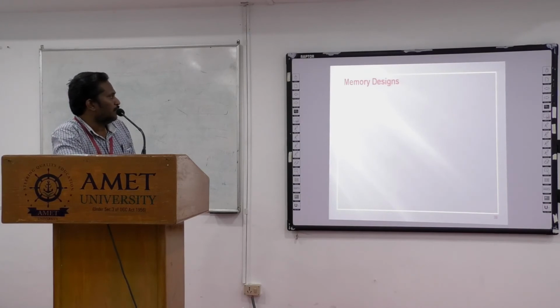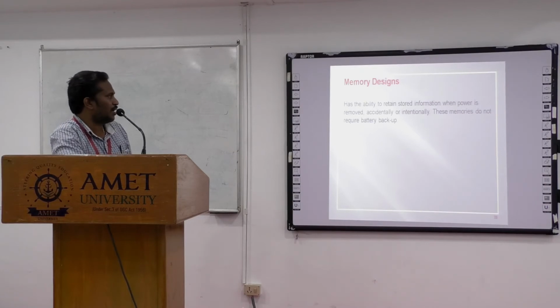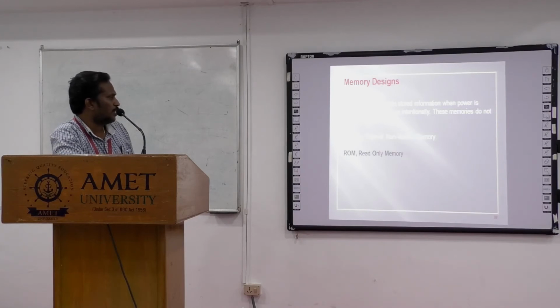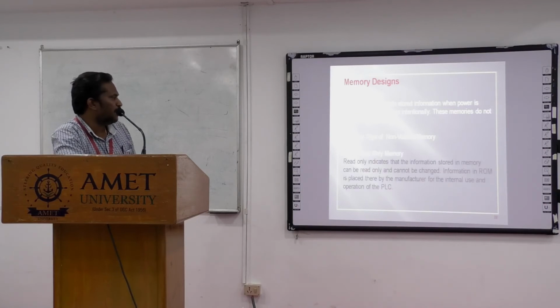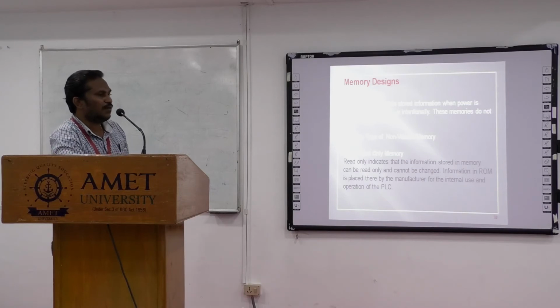The second one is non-volatile. The non-volatile memory has the ability to retain stored information when power is removed, accidentally or intentionally. These memories do not require battery backup. A common type of non-volatile memory is ROM, the expansion of ROM is read-only memory. Read-only indicates that information stored in the memory can only be read and cannot be changed. Information in ROM is placed there by the manufacturer for the internal use and operation of the PLC. Normally, the PLC will have an operating system, and the operating system will be stored in the ROM.